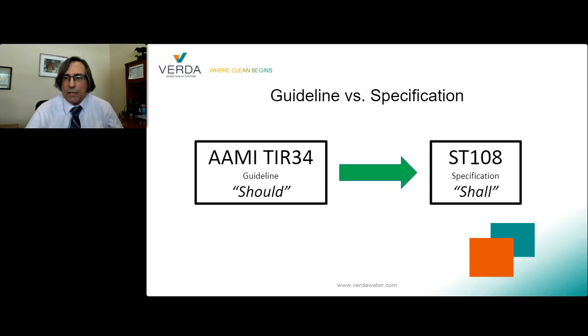As an example, if you haven't been testing with correct frequency for bacteria in your critical water plumbing, you do it and discover you're out of specification. An immediate corrective action could be to stop using critical water by changing the cycle and the relevant pieces of equipment to eliminate a final rinse with this type of water. At the processing sinks, you could use bagged or bottled sterile water. You might have to increase your level of inspection of the instruments after decontamination, and you might experience a higher level of rejection because of the corrective action, but it will address the immediate problem of using contaminated water to process instruments.